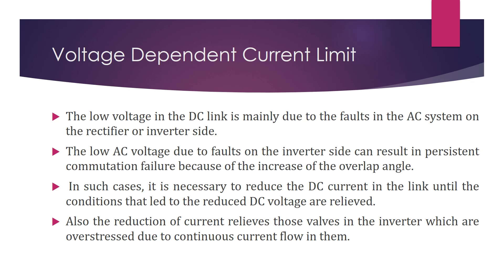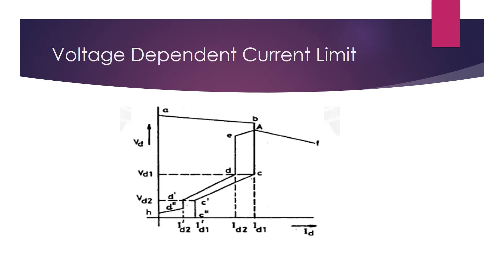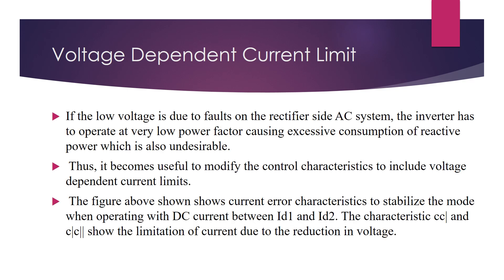The reduction of current relieves those valves in the inverter which are overstressed due to continuous current flow. The voltage dependent current limit characteristics of both stations are shown. If low voltage is due to a fault on the rectifier side AC system, the inverter has to operate at a very low power factor, causing excessive consumption of reactive power, which is undesirable. Thus, it becomes useful to modify the control characteristics to include voltage dependent current limits.